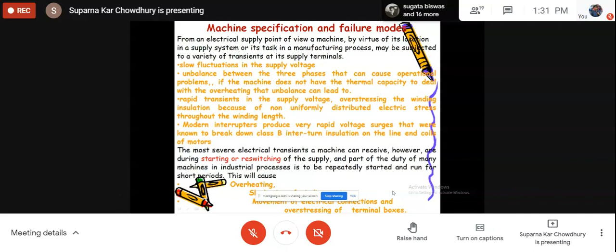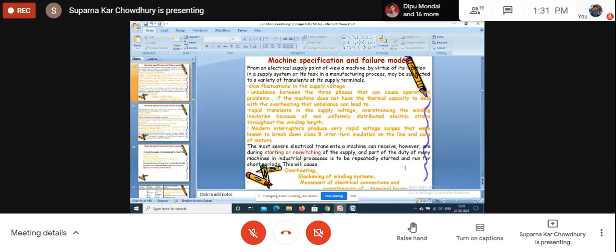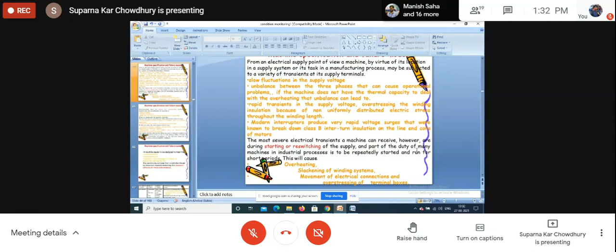But even then, the main transient which the machine is subjected to is starting or re-switching in the case of an intermittent duty cycle. So when selecting a motor, the duty cycle of the load should be known properly. Part of the duty of many machines in industrial processes is to rapidly start and run for short periods. This causes overheating, slackening of winding system, movement of electrical connections, and overstressing of terminal boxes. So if the machine is to be used for frequent starting, you have to be careful in selecting the motor.